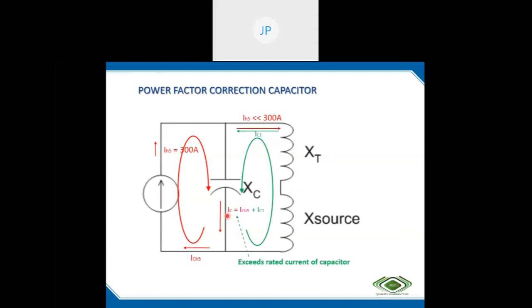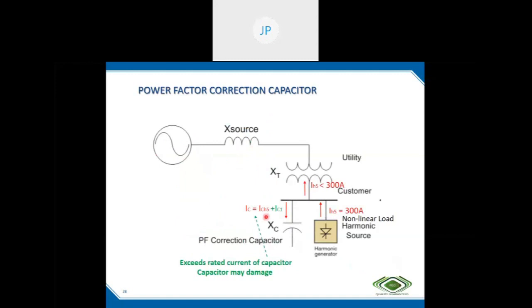The capacitor current will be the sum of the harmonic portion and the load current. But the capacitor is rated only for this current. It's a load current, so the net current will exceed the rated current. We can see in the figure here also that the net current exceeds. One portion flows like this, the other portion flows like this, and the total fundamental and harmonic current exceeds the rated current, so it may damage. There is a chance of damage and explosion.